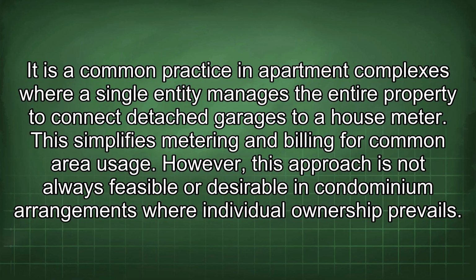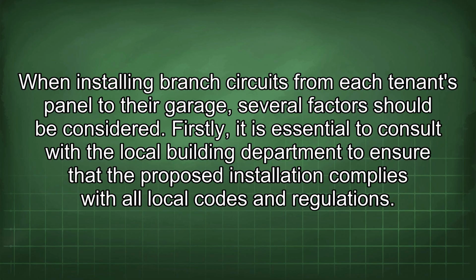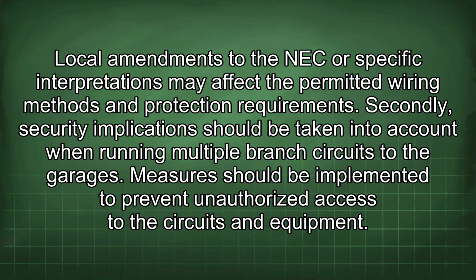However, this approach is not always feasible or desirable in condominium arrangements where individual ownership prevails. When installing branch circuits from each tenant's panel to their garage, several factors should be considered. Firstly, it is essential to consult with the local building department to ensure that the proposed installation complies with all local codes and regulations. Local amendments to the NEC or specific interpretations may affect the permitted wiring methods and protection requirements. Secondly, security implications should be taken into account when running multiple branch circuits to the garages.